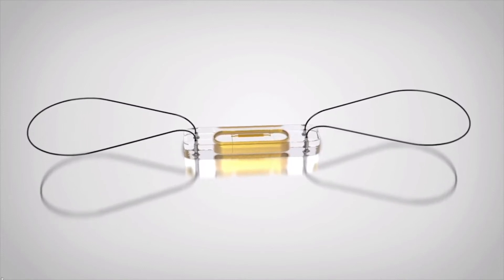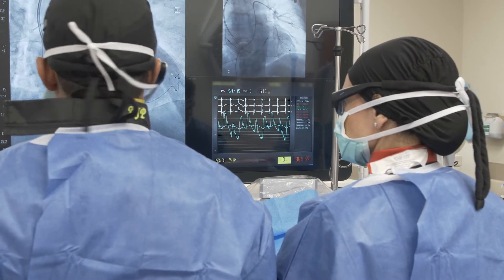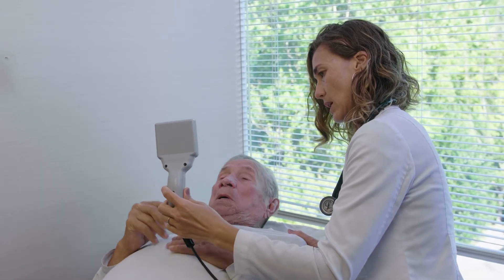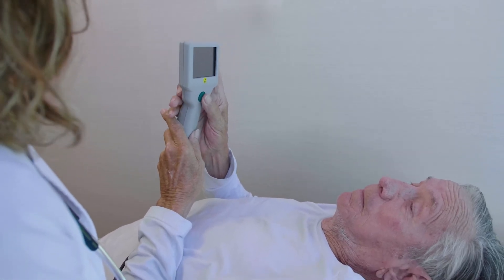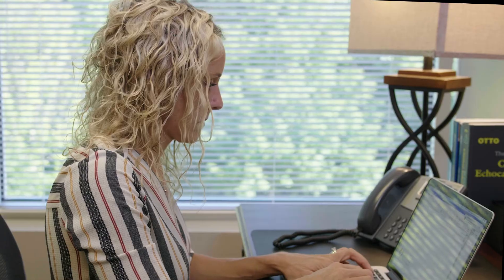CardioMEMS is the first and so far the only FDA-approved wireless implantable heart failure sensor. The device has two components. The actual pulmonary artery sensor is about 15 millimeters — the size of a paper clip — inserted by an interventional cardiologist into the pulmonary artery. It's calibrated to the pressures in the pulmonary artery, and then the patient receives a receiver. We call it the pillow, because essentially they wake up every morning and lay down on it. Within a minute, the pillow receives information from the sensor and tells us what their PA pressures are.